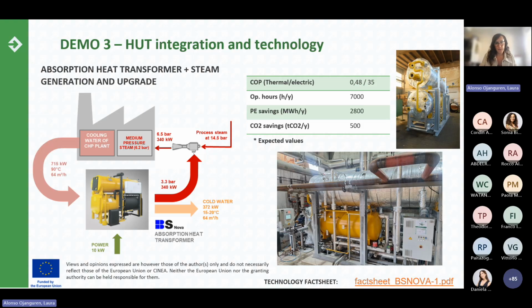In the heat transformer, we upgrade heat to a higher temperature level, around 145 degrees, and we provide hot water. But what is needed in the plant is steam. So we produce this steam externally to the system in a flash tank, in which we produce low pressure steam at around 3.3 bar. And then we combine this system with a thermocompressor, which also uses high pressure steam, which is available in the plant. This high pressure steam mixes with the low pressure steam we produce, and so we get the final steam at 6.5 bar, which is the pressure level needed in the process. And this is injected into the medium pressure steam header in the plant.